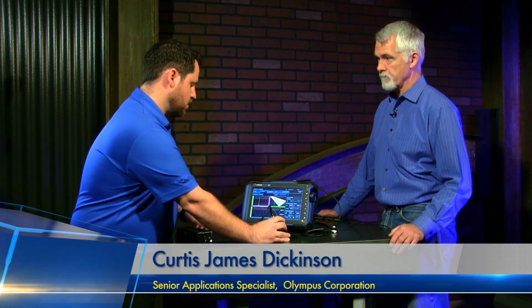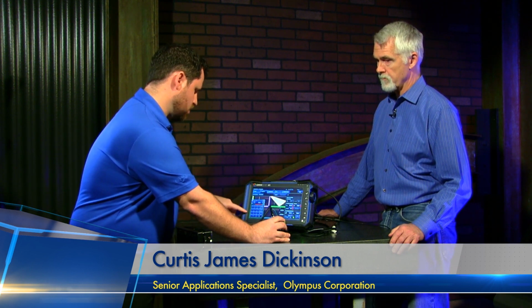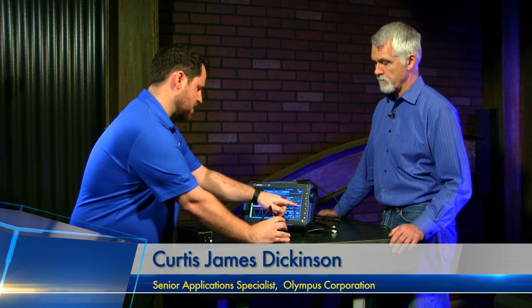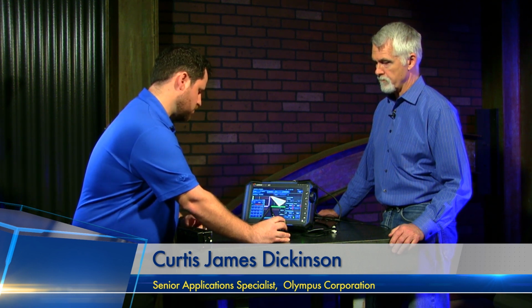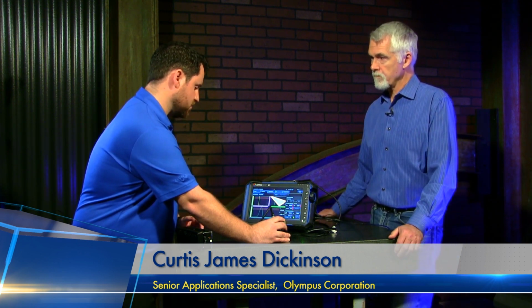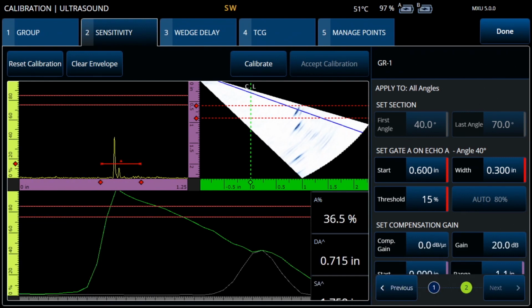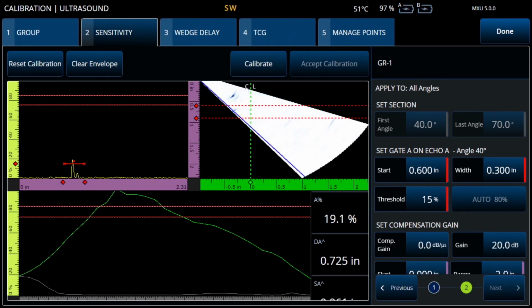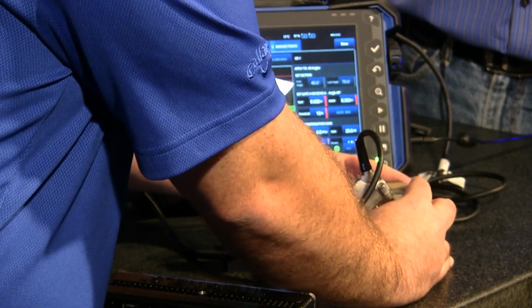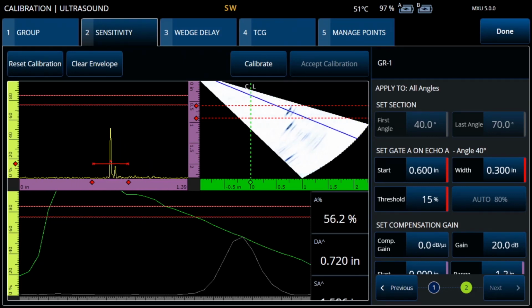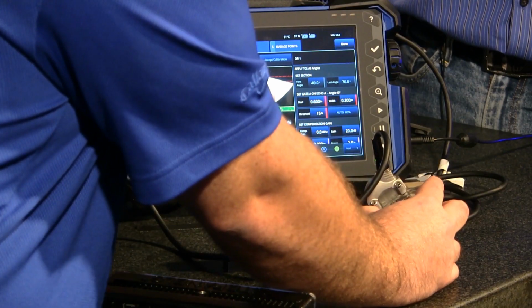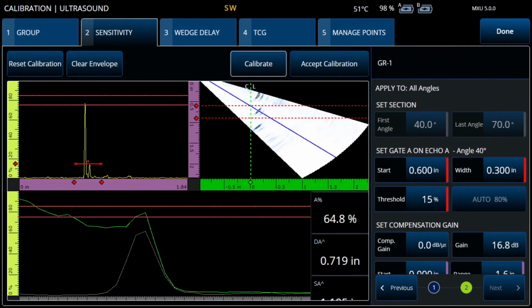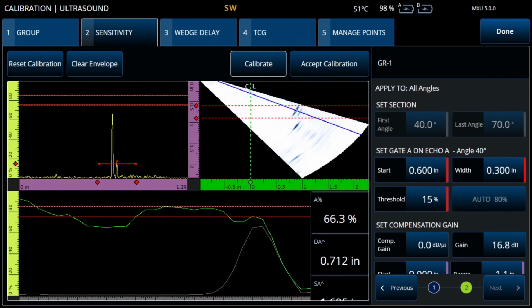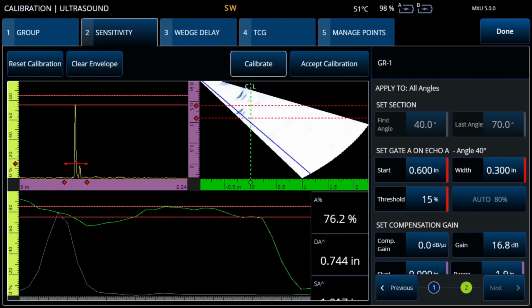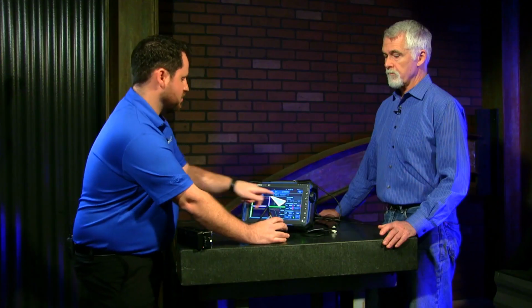So if I just quickly run through one of those calibrations here, this is what we would call a sensitivity calibration, where instead of one particular position having a different amplitude reading across all of the angles, we want that amplitude reading to be the same across all those angles. So I can very, very quickly show the instrument an indication, collect the amplitude reading all the way across, and as I complete that, the instrument will quickly adjust and compensate for that amplitude. I'm sitting in a kind of funky position, but really the benefit of this system is just the speed with which that can be done. We can accept that calibration.